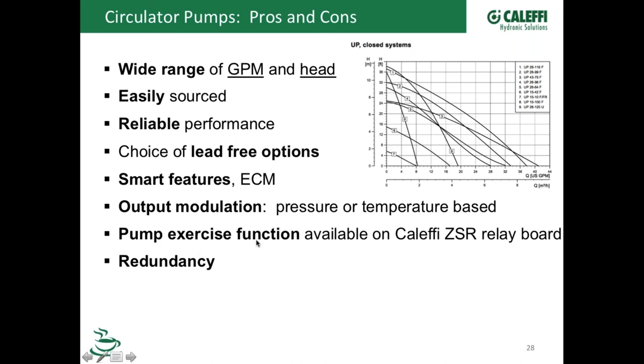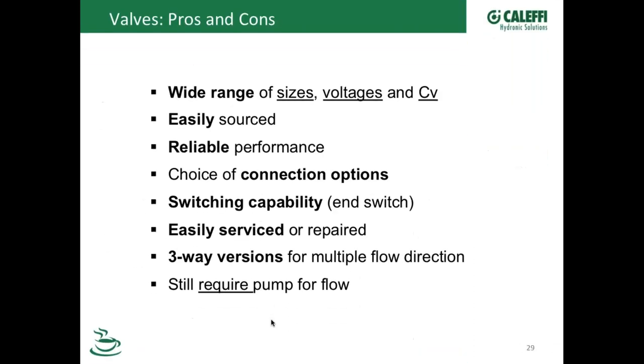The other thing is exercising pumps occasionally, and the relay boxes from Caleffi have an exercise function in there that will run that pump. I think it's every 72 hours, if there isn't a call for heat, it'll turn it on for 15 or 30 seconds, Cody? Yep, that is correct. Yeah, and both of our boards, whether it be a pump board or a valve board, will do it.